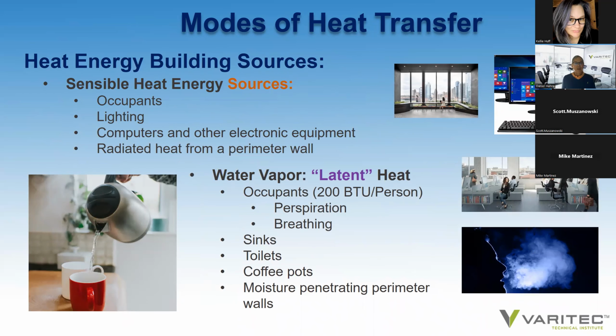So what are the sensible heat energy sources in the building that will provide the energy that needs to be moved from the building to outdoors? Wherever you have occupants with a body temperature of 98 degrees, they're adding heat energy to a space. Lighting, where you have the source of electrical power, will cause a heat component. Computers, electrical equipment, radiated heat from perimeter walls on hot days: all of these factors increase heat energy within a building. What increases the amount of water vapor or latent heat in the building? Occupants through perspiration and breathing, sinks, toilets, coffee pots, anywhere where there's exposed water in a space will contribute to an increase of water vapor.